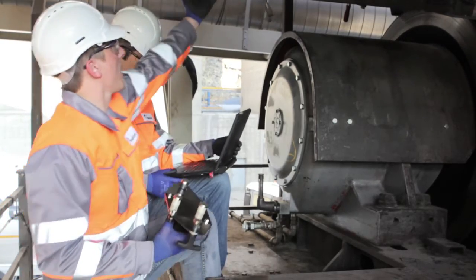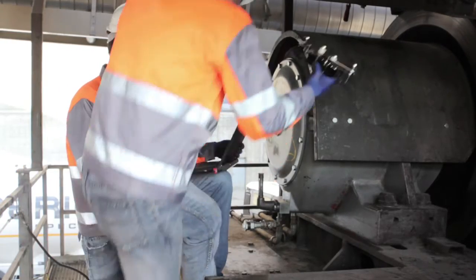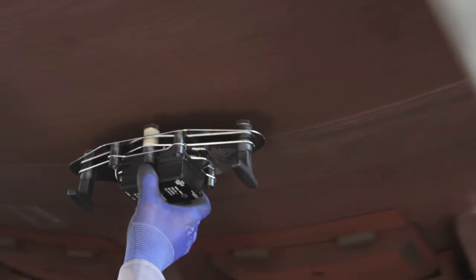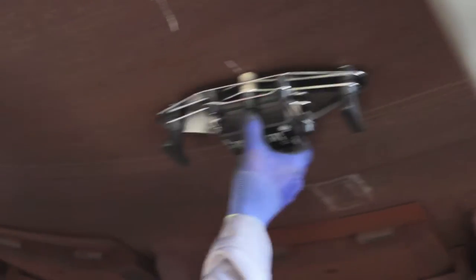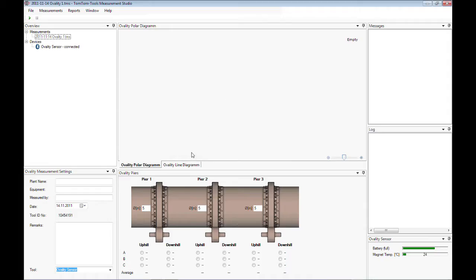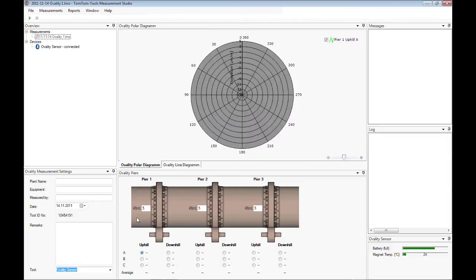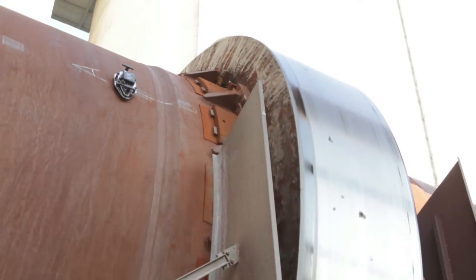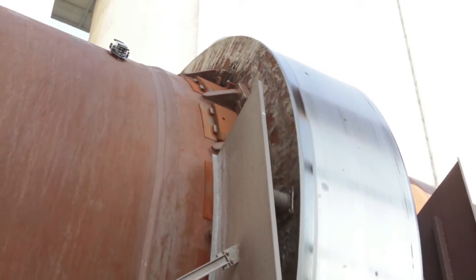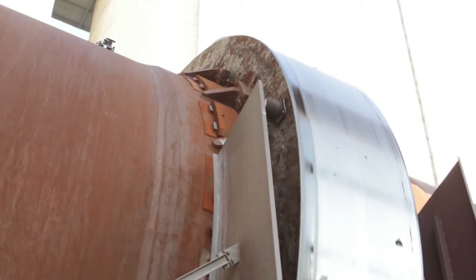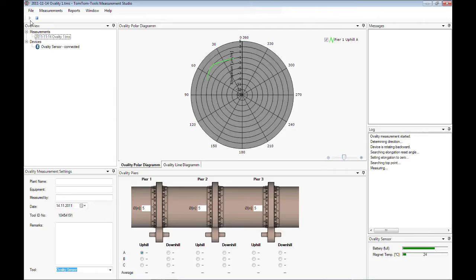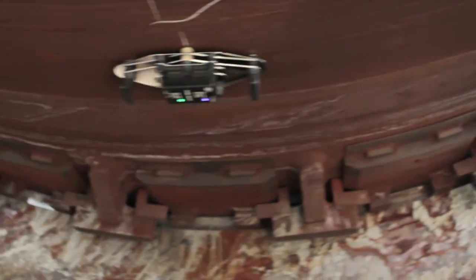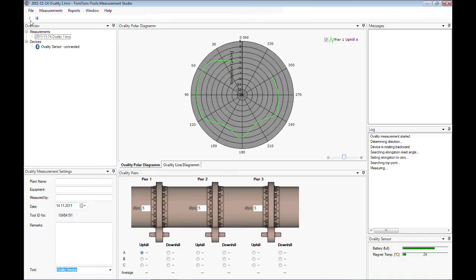Place the tool on the first of the three previously marked reference points, in this case point A. Then start the measurement with the start button or by pushing F5. The data logging starts when the tool reaches the top point. The measured points are displayed continuously on the screen until the tool reaches the top point for a second time.